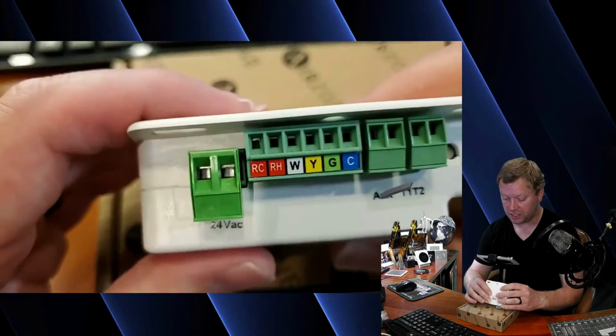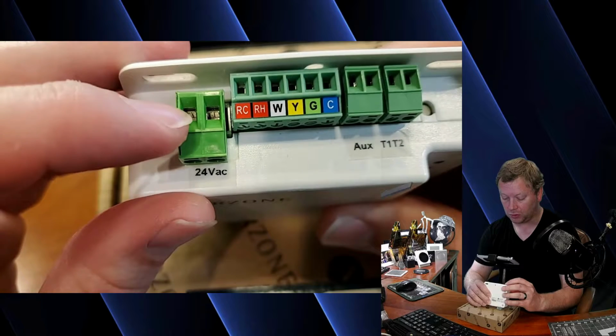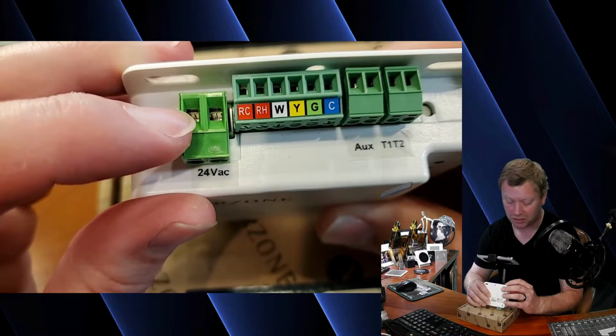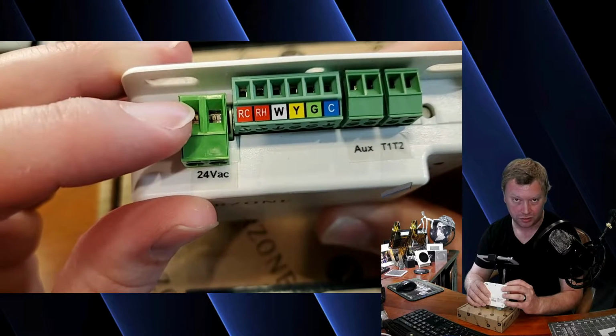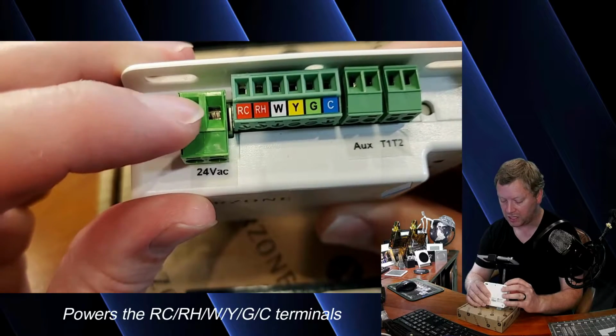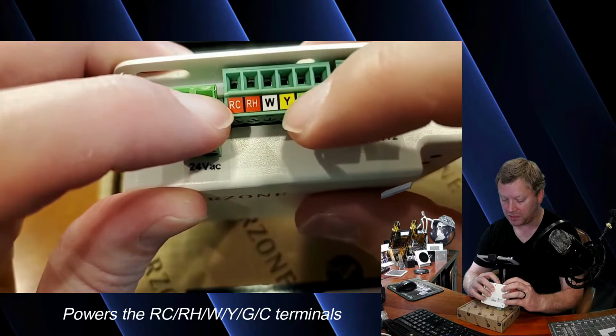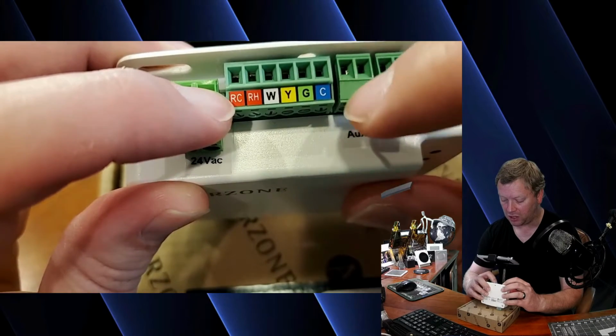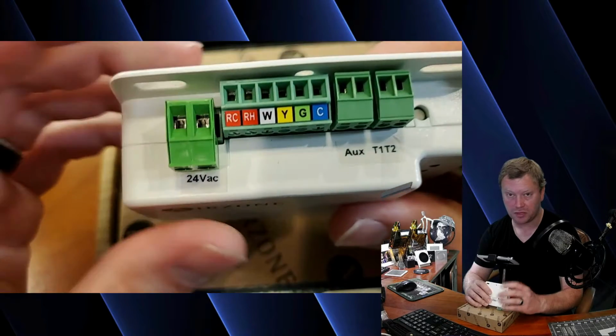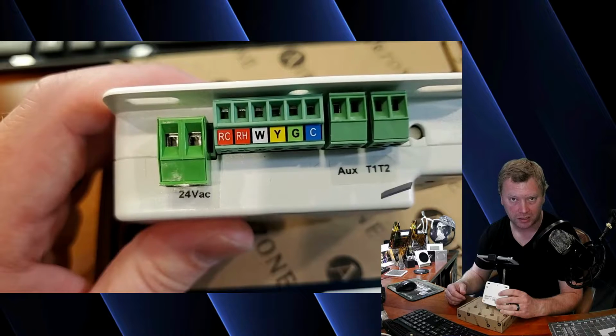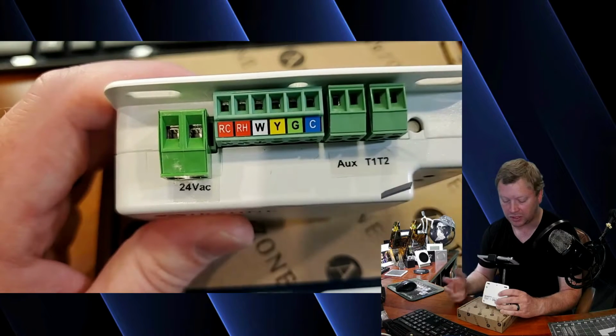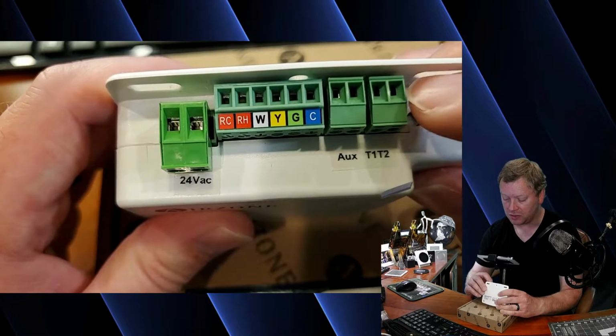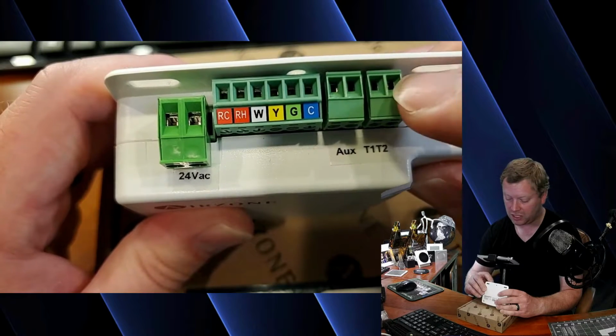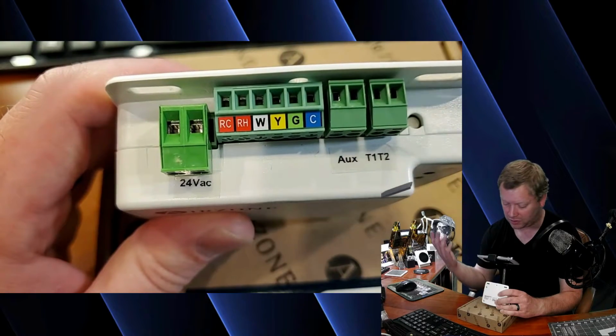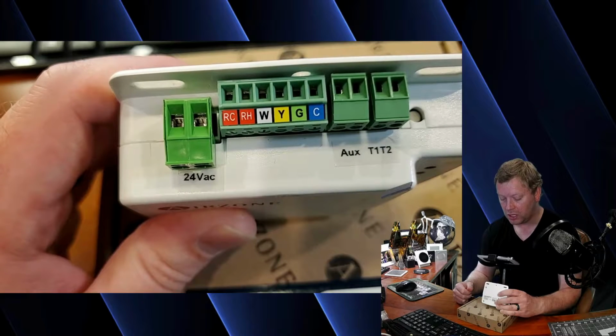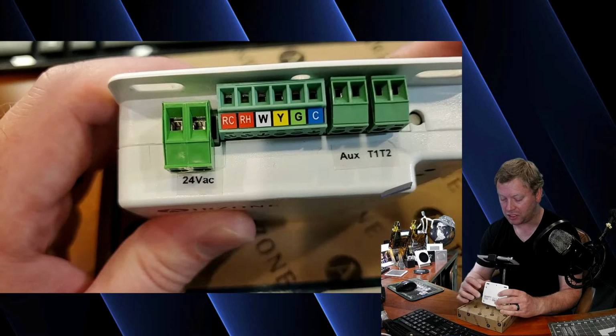On the other side, here's your 24 volts. This is 24 volts that you need in order to power the thermostat. Then you have your normal thermostat wires here. You have an auxiliary option, so maybe you want to connect an auxiliary heater or anything like that. And then this is your T1, T2 forced off connections that you would normally have on an indoor unit board. So you get pretty much everything that you need here.